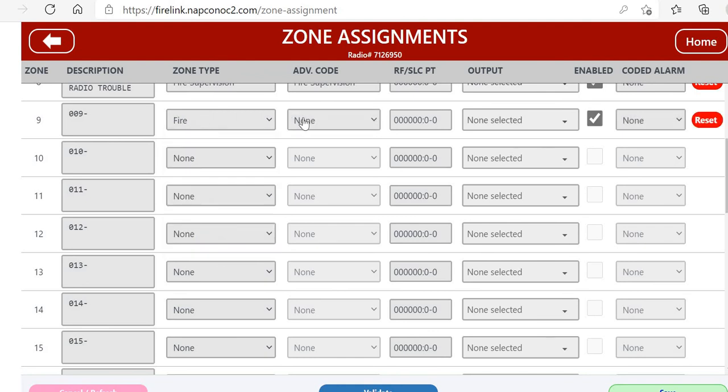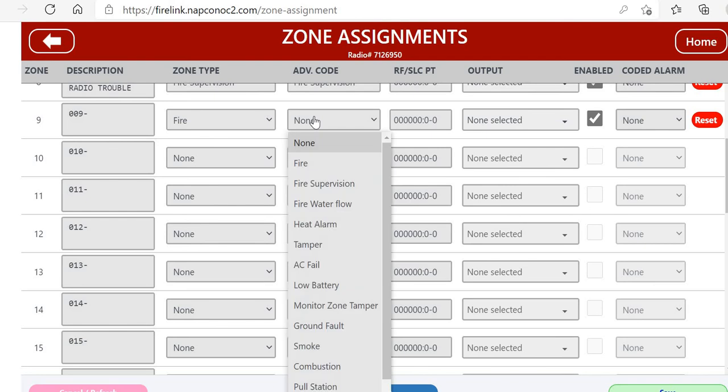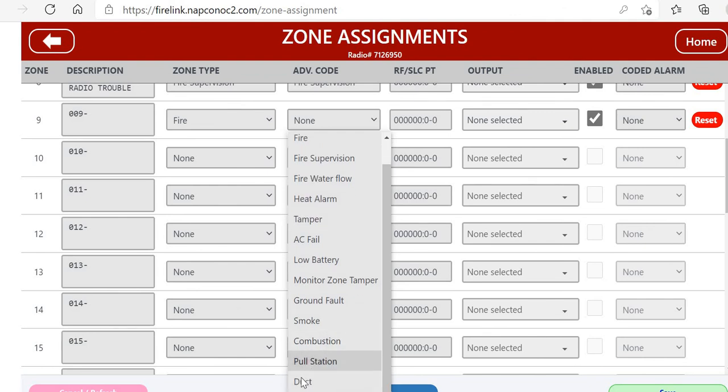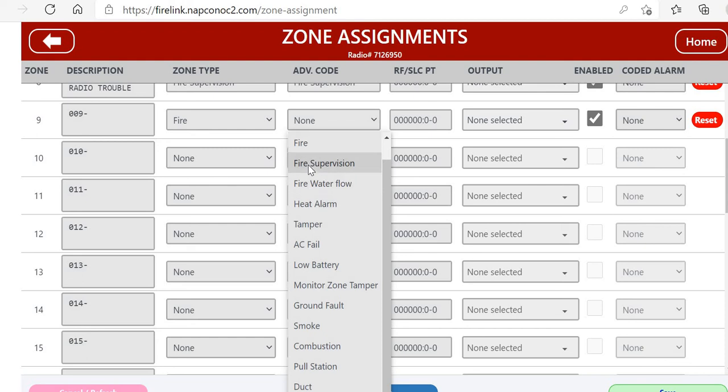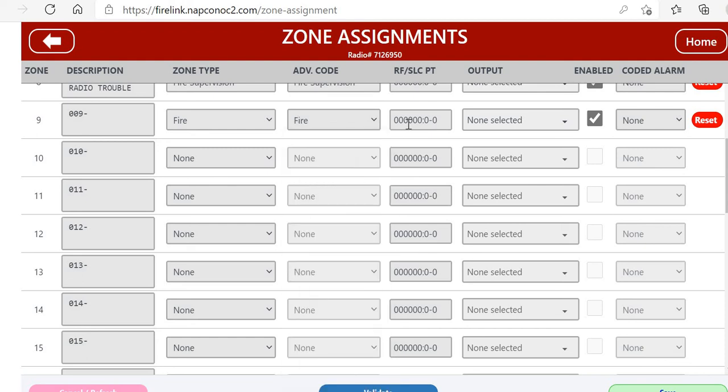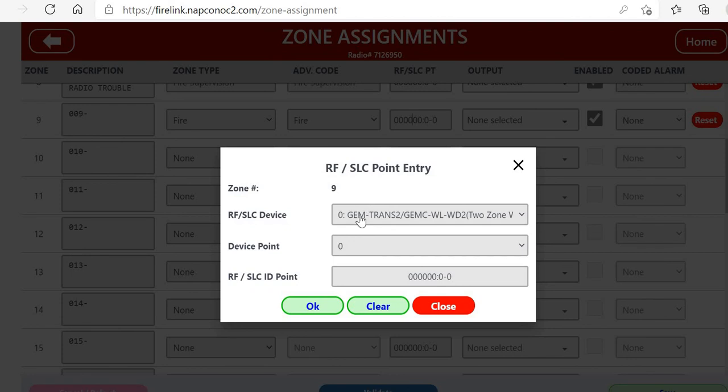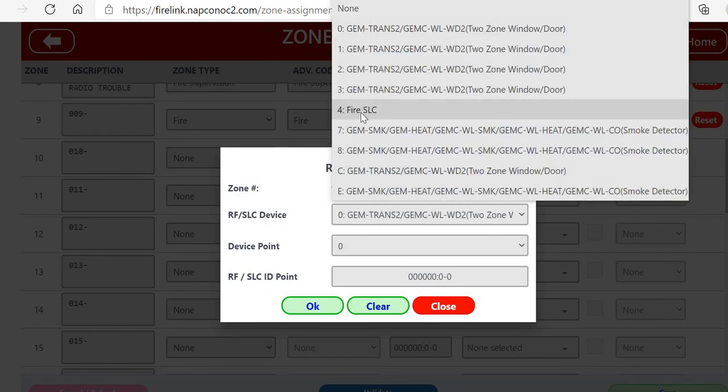First, and this applies to all of the different kinds of zones, we're going to pick the zone type. We're going to make this a fire zone, advanced code of fire. That's a general fire, but we also have pull station, ducts, different water flow, supervisory for those type of zones.